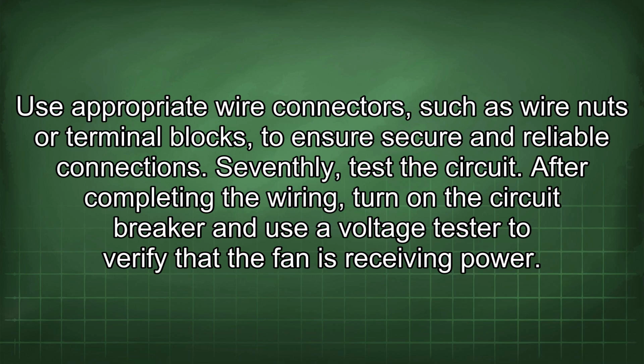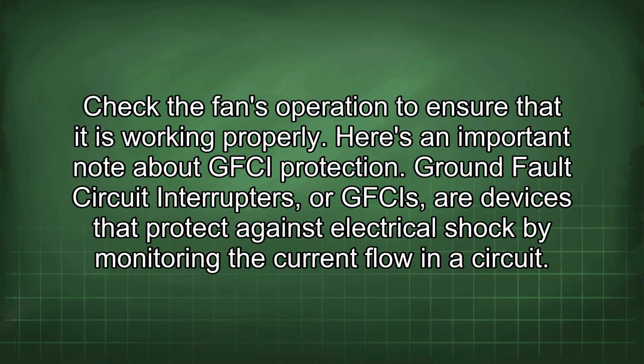Seventhly, test the circuit. After completing the wiring, turn on the circuit breaker and use a voltage tester to verify that the fan is receiving power. Check the fan's operation to ensure that it is working properly. Here's an important note about GFCI protection. Ground fault circuit interrupters, or GFCIs, are devices that protect against electrical shock by monitoring the current flow in a circuit.